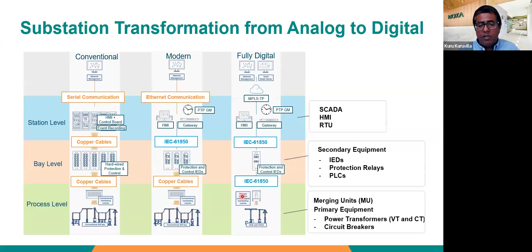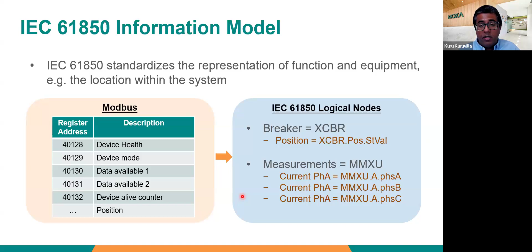And then what you would call a fully digital substation is when all the communication and all the data acquisition is digital, which primarily means that the end user equipment, whether it's measuring equipment or protection equipment, needs to be able to be integrated into the digital network. Once that happens, you can call that a fully digital substation. IEC 61850, I think a lot of you mentioned Modbus as something that you see a lot in the systems today. Again, IEC 61850 uses standardization, more descriptive, standard terminology to designate the various data points.